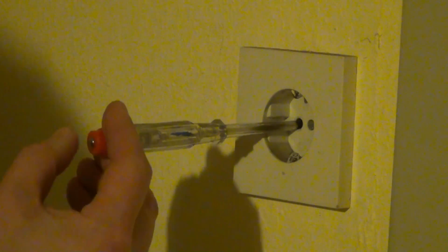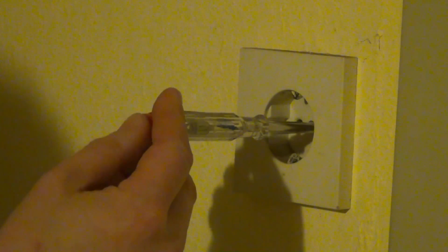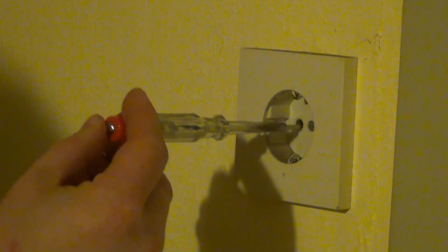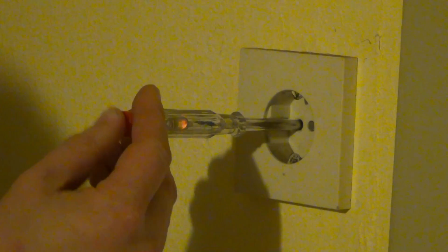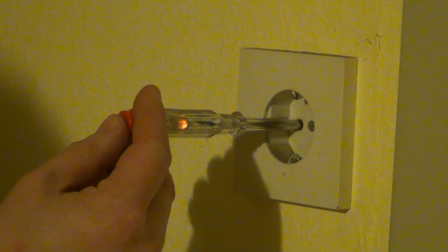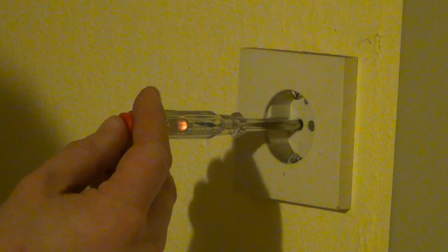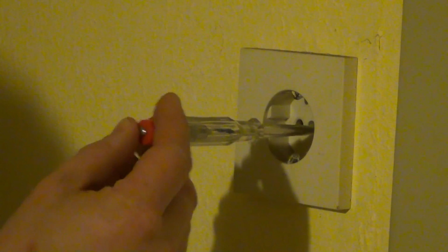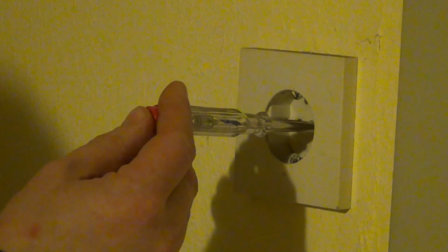This is a neon lamp type mains tester in the form of a screwdriver. When you connect it to the contacts in an electric outlet while putting your finger on the metal piece on top of the screwdriver, and it happens so that the tester has contact to phase, a little neon lamp inside the tester will light up, as can be seen here. When you connect it to the so-called neutral, however, it doesn't light up.